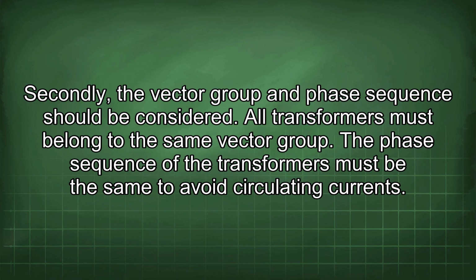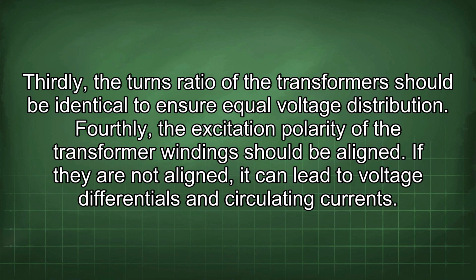Secondly, the vector group and phase sequence should be considered. All transformers must belong to the same vector group. The phase sequence of the transformers must be the same to avoid circulating currents. Thirdly, the turns ratio of the transformers should be identical to ensure equal voltage distribution. Fourthly, the excitation polarity of the transformer windings should be aligned. If they are not aligned, it can lead to voltage differentials and circulating currents.